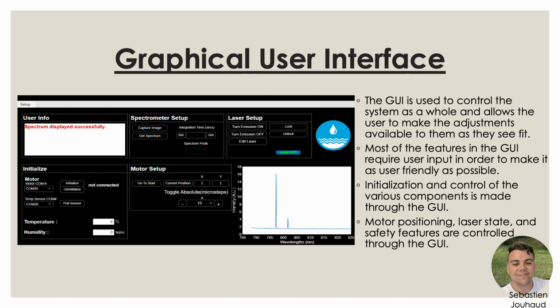As for the spectrometer setup, the spectrometer isn't controlled through serial commands. It's essentially always plugged in and ready to go with the camera as long as there's power to it. So when you hit capture image, assuming the laser is on and the detector is detecting some kind of signal, the detector will take that image, display it on your screen, and allow you to save it to a specific folder that you want.